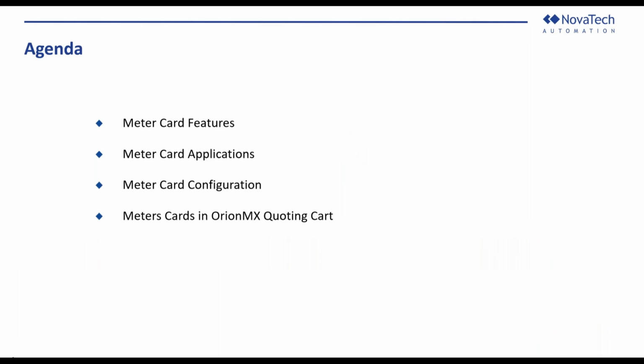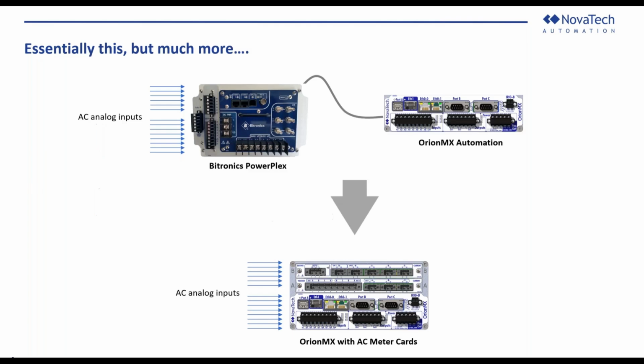The agenda, we'll talk about some of the features of the meter card, then move on to applications, configuration, and we'll show you how it appears in the quoting cart. Meter card is a marriage between Bitronics instrumentation and OrionMX. We repackage the Bitronics PowerPlex. The PowerPlex is very much like a panel meter, like a 50 or 60 series panel meter, but it has some additional capability where it can actually measure the voltages on two buses and the currents on one line. Gives us more flexibility in some applications that we'll talk about.